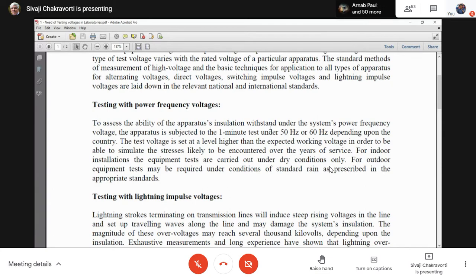Then you can always ask me, what will be the test voltage? Yes, as an engineer, let me stress this point. As an engineer, in your entire life, wherever you are working, doesn't matter, you have to follow the standards. In India, we have the Bureau of Indian Standards, and they issue the standards for all sorts of equipment. So if you are manufacturing something and you try to sell it, then the customer will say that you have to prove that your equipment follows certain standards by certain testing. And this testing has to be done in a third-party laboratory. It means if I am the manufacturer, I cannot do that test in my lab, even if I am a big company. I have to go to a third-party lab and do that testing. So for that, I need to generate high voltage in the lab.